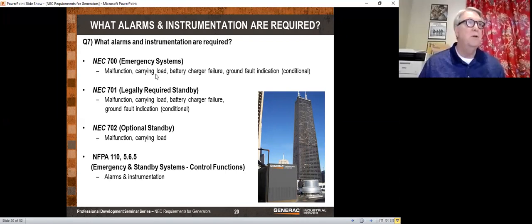And so if the transfer switch has a light that says you're in the emergency, or actually it's called normal and emergency, and it tells you which position it's in, that satisfies that. Battery charger failure and ground fault indication. We'll talk about ground fault later. Notice here that it does not say ground fault protection. We don't put ground fault protection on generators.